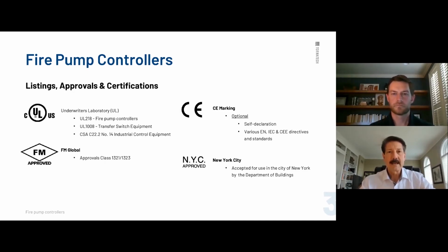NYC, New York City, has requirements. So we do have to go into New York City, meet the powers that be, and present and do testing based on their requirements before we can actually ship anything into New York City itself. And that goes for any manufacturer. And City of Chicago has requirements. It's not really a listing or an approval, but it's an option add. Option B11 has an internally mounted alarm panel. And you go out to Los Angeles or Denver, they require additional remote alarm contacts. We'll get into that later.